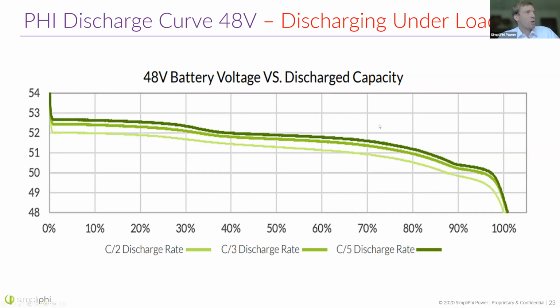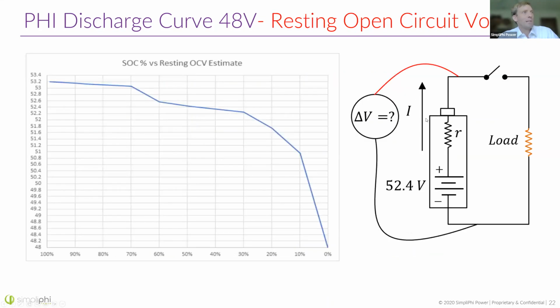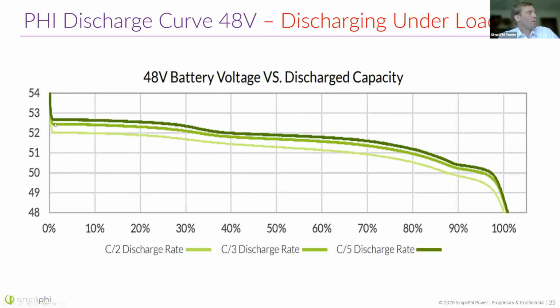If we slow the discharge rate down, I is smaller, and the voltage drop across the internal resistor is smaller. That means the voltage measured on the outside, on the connecting wires, is going to be higher. So there's a significant difference between discharging at 37.5 amps versus 25 amps, which is a C/3 discharge rate. At 50% state of charge, you're about 0.3 of a volt higher.